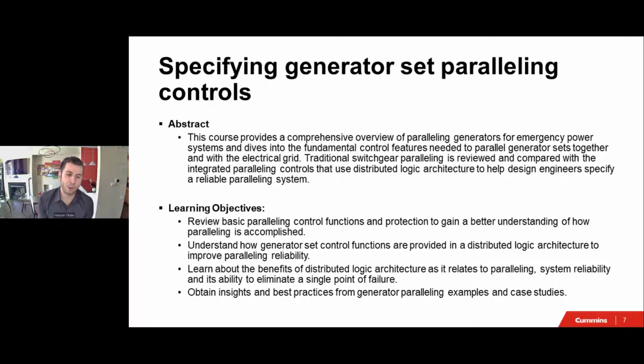I do have a slide for you on paralleling generators with the utility. And then we'll talk about traditional paralleling and compare that with the distributed logic architecture. So the objectives are to review basic paralleling controls to gain a better understanding of how paralleling is accomplished. Understand how generator set control functions are provided in a distributed logic architecture to improve the reliability of the system. And we'll learn about the benefits of distributed logic architecture as it relates to paralleling, system reliability, and the ability to eliminate single point of failure. And at the end, I have this one use case to share with you.